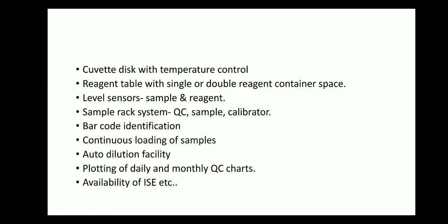Then continuous loading of samples. Okay, suppose now you get 5 samples, you put them in the analyzer, you need not wait for those 5 samples to be completed. After you load the samples, once the testing process has started, if you receive some more samples, you need not wait, you can just load these samples also. So once those 5 samples are finished, these also are carried out. Okay, so the continuous loading of samples facility is there.